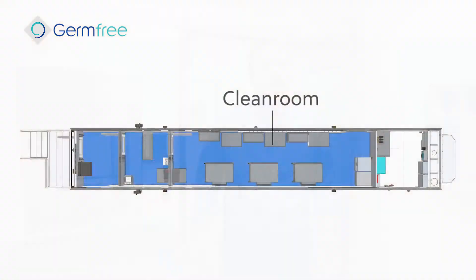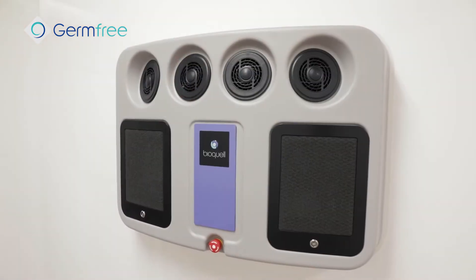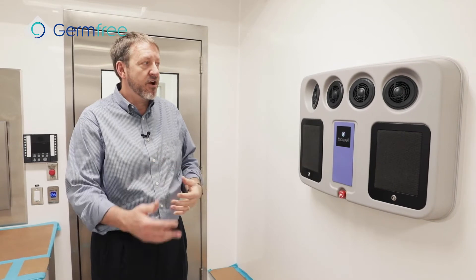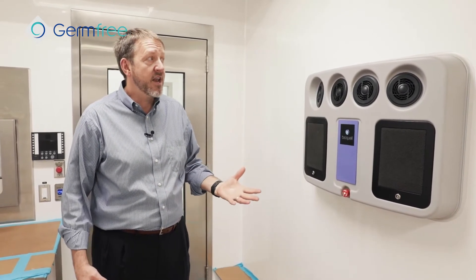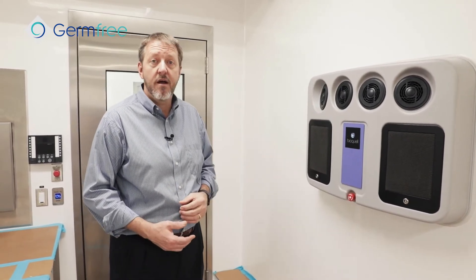Now we're in the main cleanroom. This is designed to be either Grade C or could even be Grade B in some cases, which is actually ISO 5 at rest — a very flexible design once again. As we come in, one of the first features you see is the Bioquell distribution unit for the VHP system. This is where the distribution actually happens. The fans are built into it to distribute the sterilant throughout the facility — a very innovative design that allows VHP sterilization to happen almost in real time. If you had to do a daily sterilization, this would be appropriate for what you're doing.